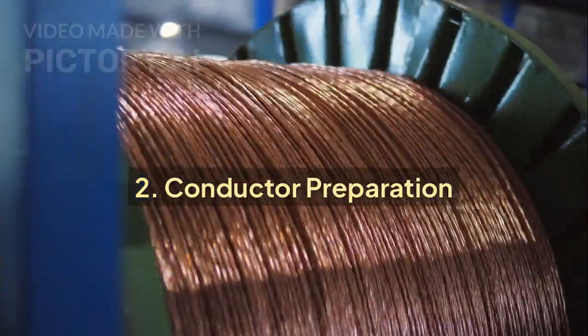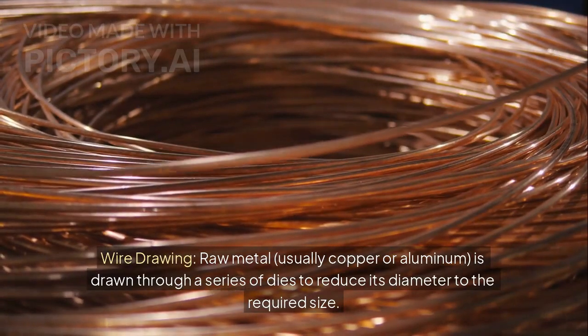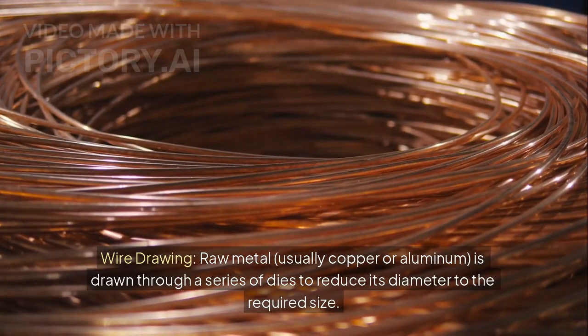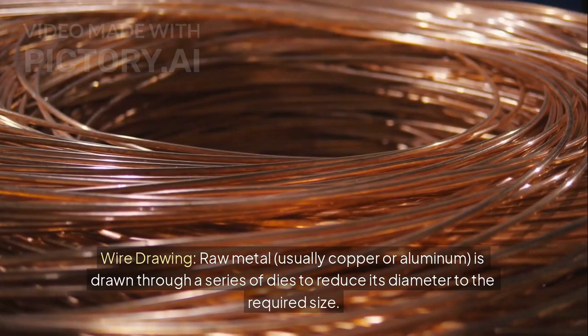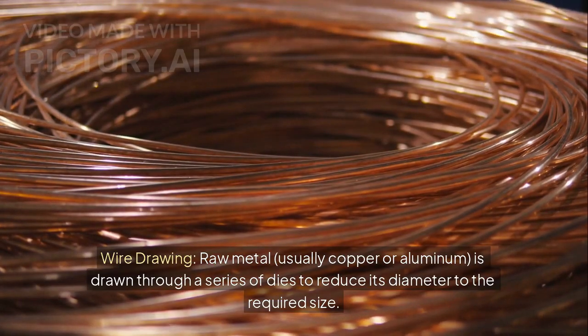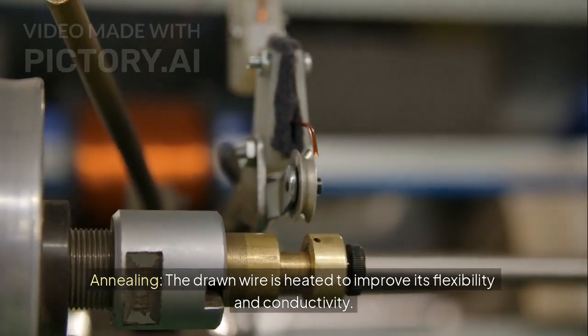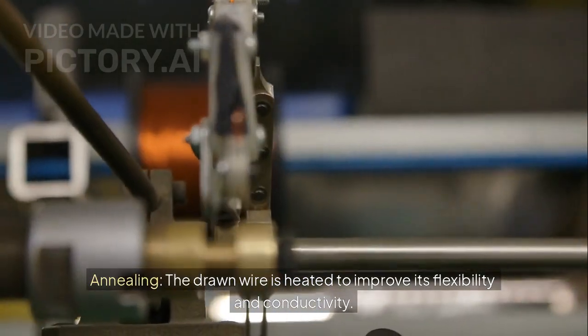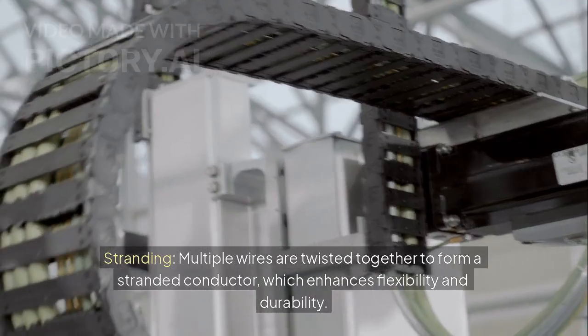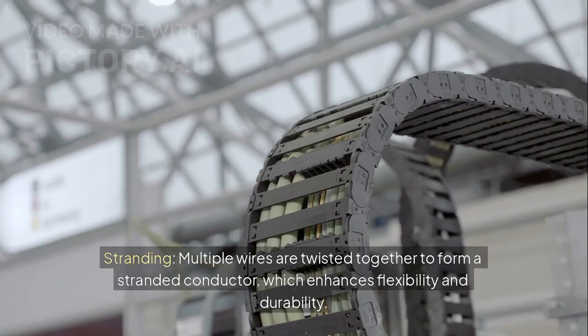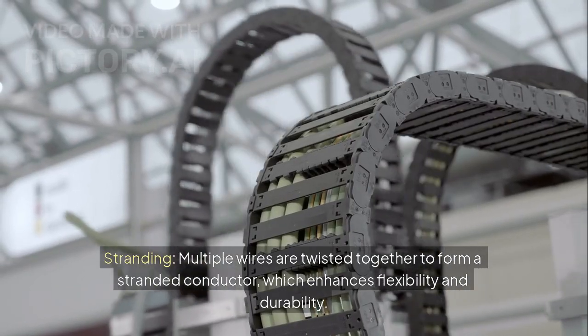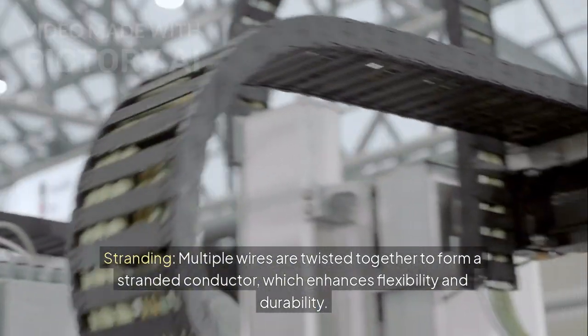2. Conductor preparation. Wire drawing. Raw metal, usually copper or aluminum, is drawn through a series of dies to reduce its diameter to the required size. Annealing. The drawn wire is heated to improve its flexibility and conductivity. Stranding. Multiple wires are twisted together to form a stranded conductor, which enhances flexibility and durability.